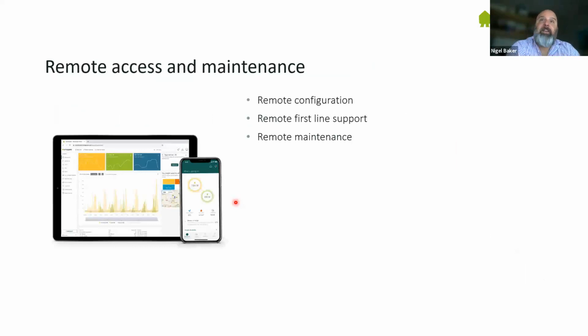A really big value add is we can do remote configuration, remote first-line support, and remote maintenance. So if the installation is done incorrectly, we can fix it remotely, and you as a customer can fix it remotely too. If the CT is the wrong way around, with incorrect polarity, you can go and change the CT on the app or on the dashboard.